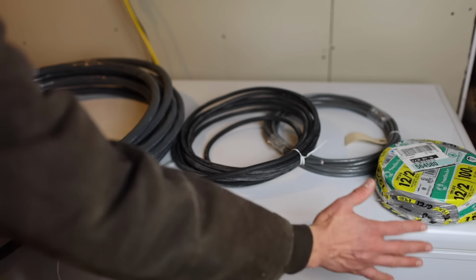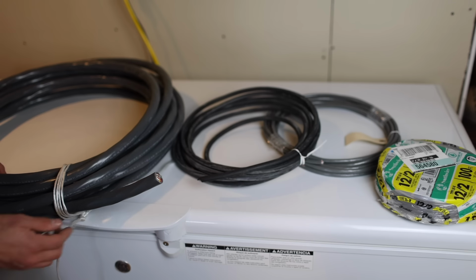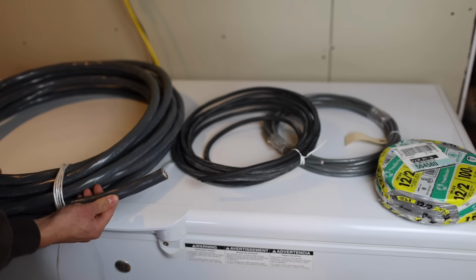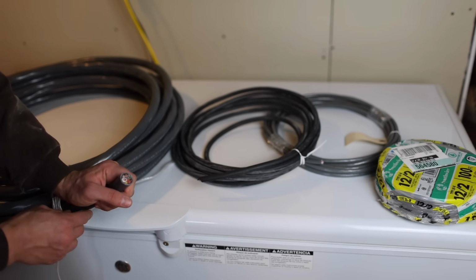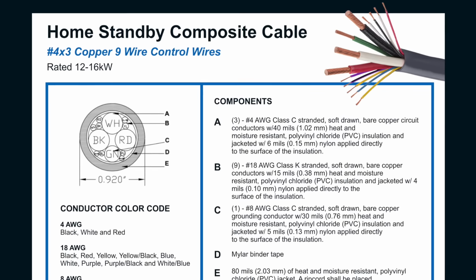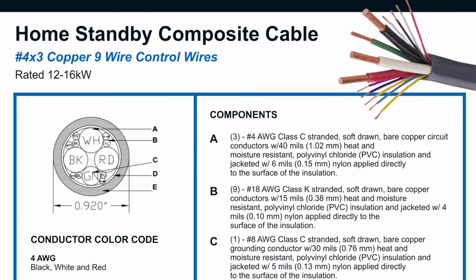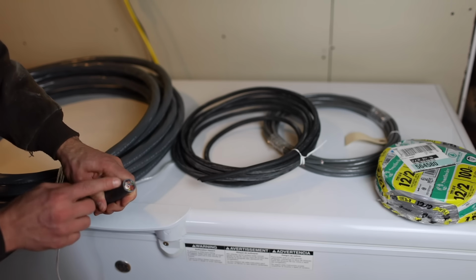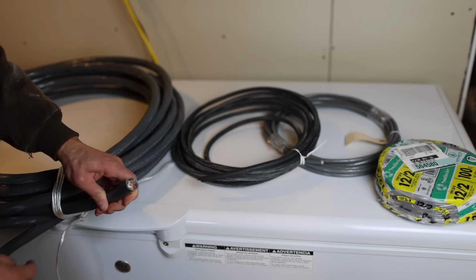Through this 2-inch conduit, I'm going to be running these 4 things. First, I have this big honkin' cable right here. This is the generator power cable. It's got 3 power wires, plus a ground, plus a bunch of wires for control circuitry. I'm going to be using these in part 2 of this series so that I can use the generator as an automatic standby generator.